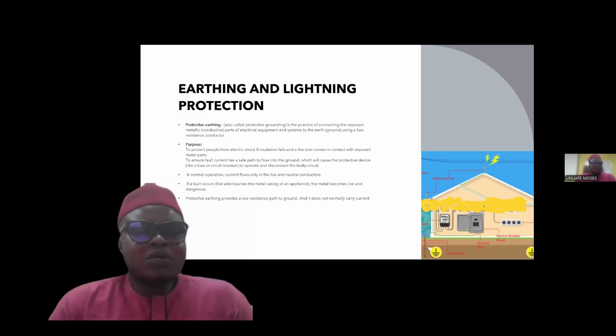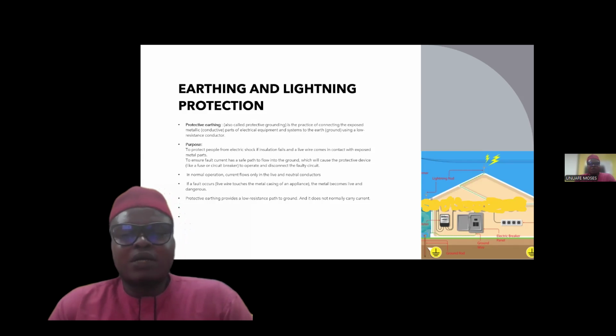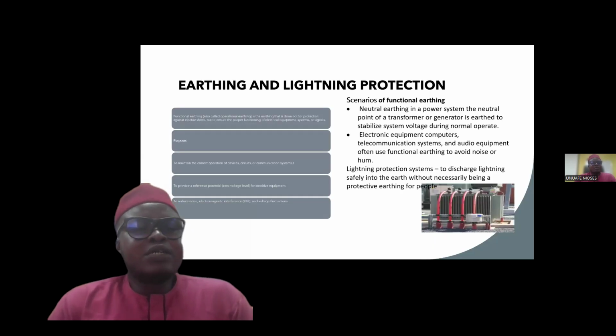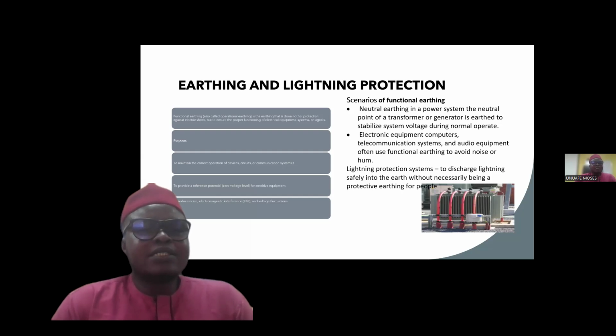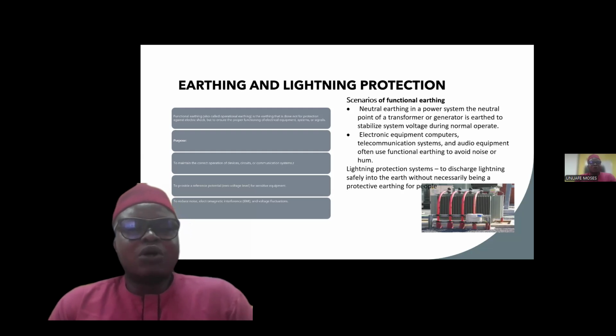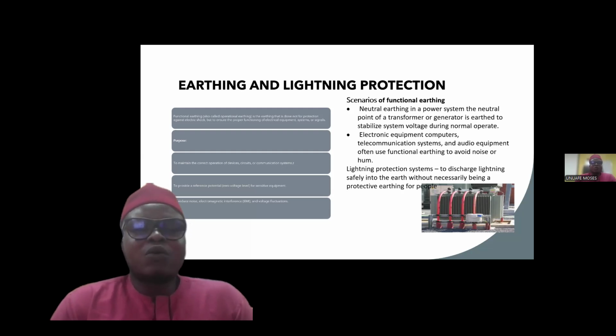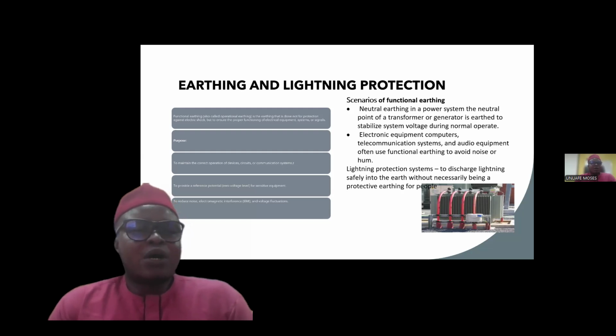There is also another reason why we need to do this. Assuming a fault occurs in an equipment or appliance, the metal becomes live and dangerous. That is why protective earthing provides a low resistance path to ground, and it does not normally carry a current. And there is a need for us to also understand functional earthing. Functional earthing is the earthing that is done not to protect against electrical shock, but to ensure the proper functioning of all electrical equipment so that they can operate optimally.